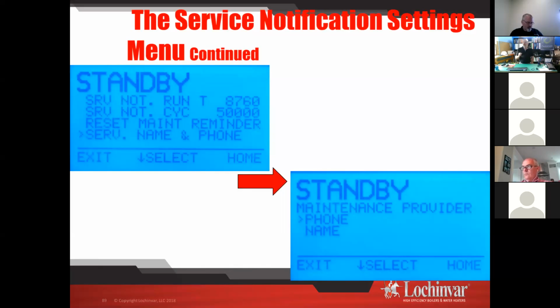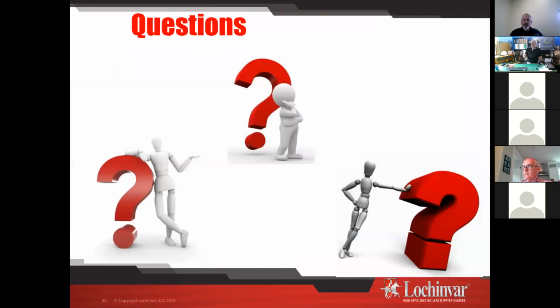But I'd recommend, if you take over a new customer and they've got a Lochinvar boiler in there, it's been in a year, 2, 3, 4 years, whatever, make sure that not only do you put your sticker on the side of the boiler, but go program your name and phone number inside of there. Otherwise, when that triggers, they'll get the old company's information.